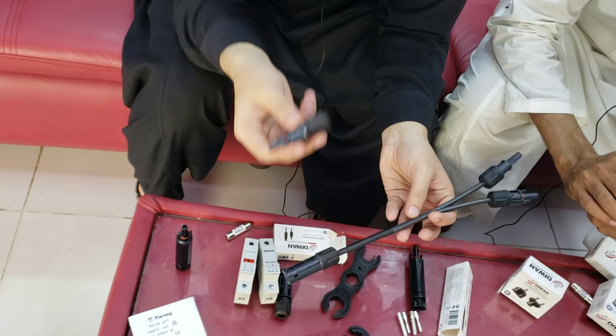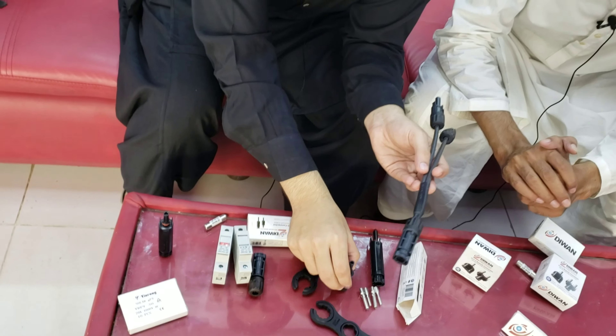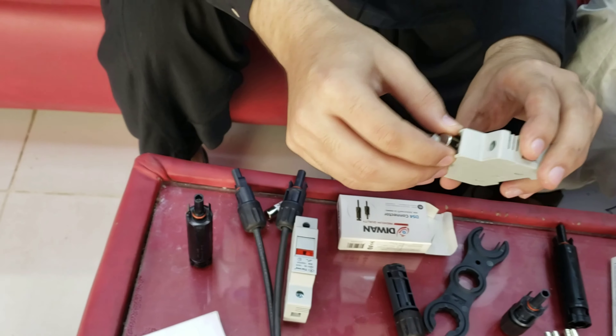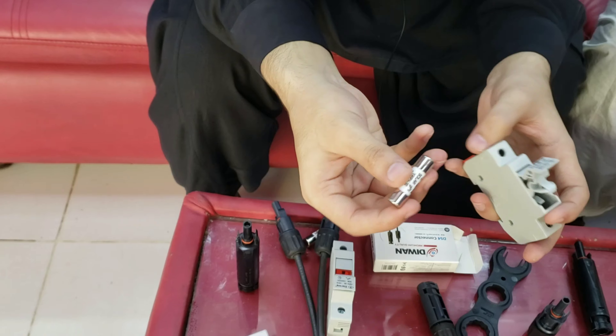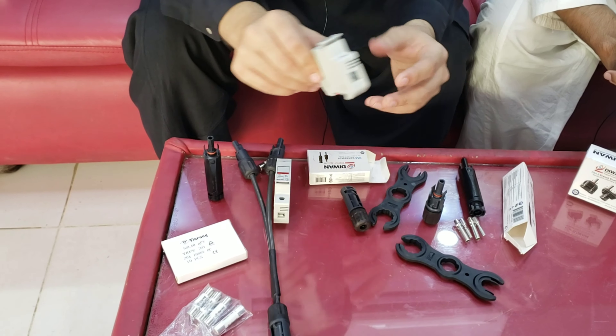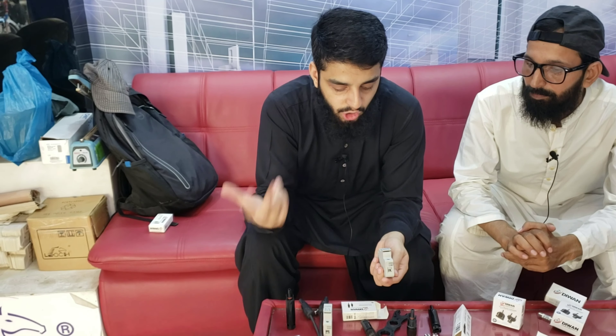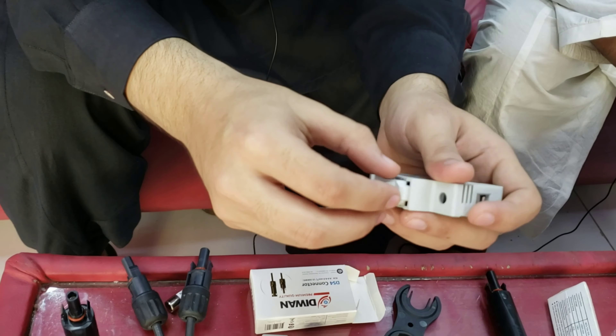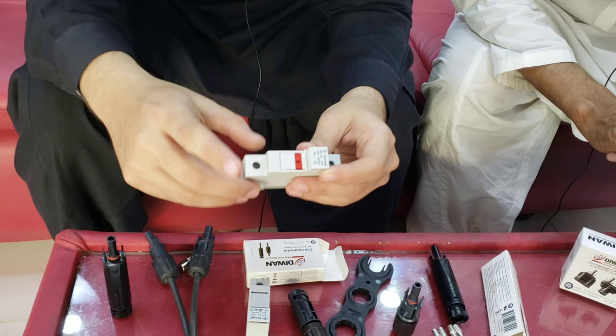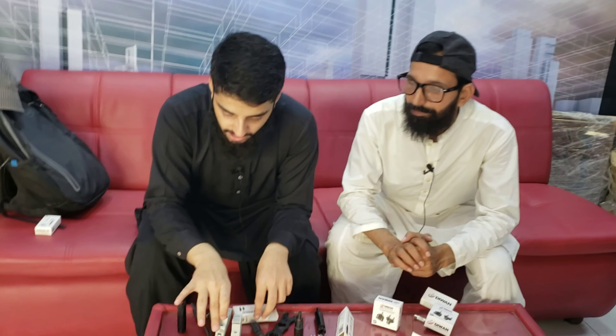The third item is the fuses. These are 1000-volt fuses that provide voltage and ampere protection — protecting your system from overload and overvoltage. The capacity is 20 ampere and 30 ampere. The fuse is TÜV, CE, and UL certified. We also have 1500-volt fuses with the same TÜV certification. The fuse base provides an indication — if the fuse is broken, it indicates that your fuse has blown.